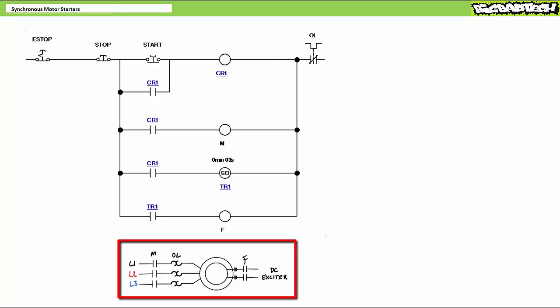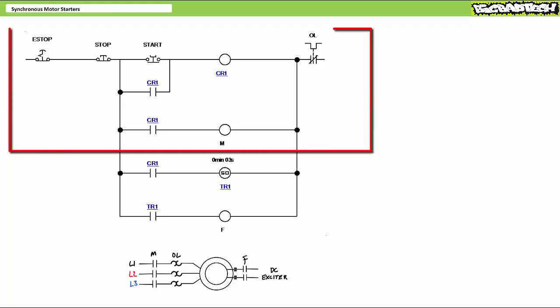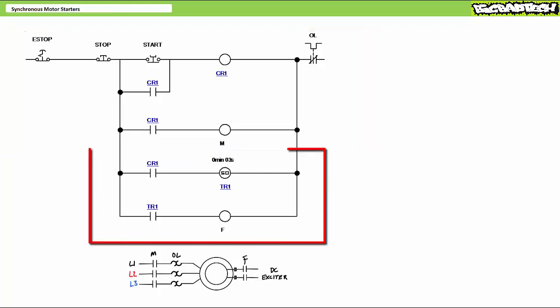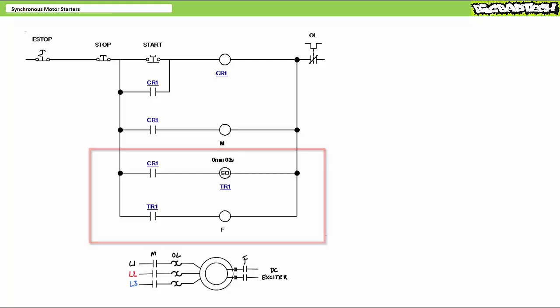Then after a predetermined period of time, say three seconds has elapsed, close the field contactor so the rotor locks into the stator's synchronous speed. The top three rungs of the pilot circuit largely concern the M contactor, whereas rungs four and five concern themselves with the timer and the field contactor.